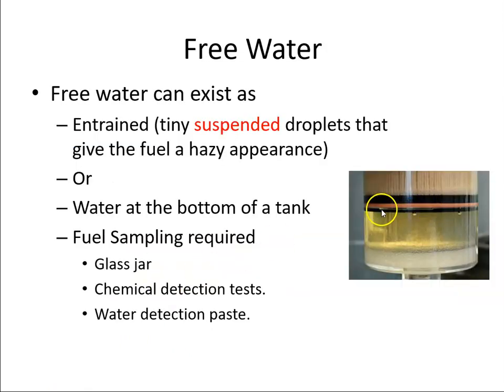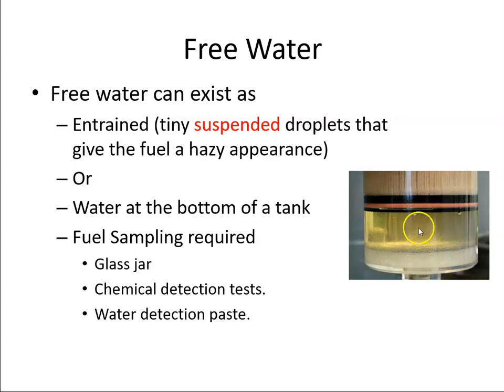Here is an example of some fuel with water visible at the bottom of the tank. This will cause operational problems, so what we need to do is sample the fuel regularly and test for water. We'll look at fuel sampling in another video.